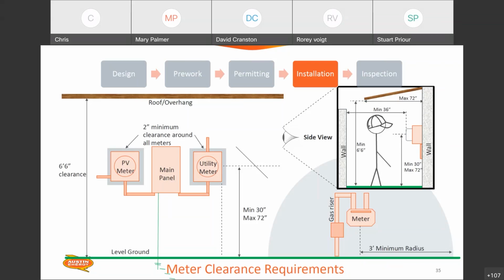You'll see the gas meter there. Regulator on that gas meter is where you need to keep everything out of a 3-foot radius from that gas regulator. That's all electrical components. Conduit, obviously EMT, you can have it run by gas meters, but anything that has a disconnecting means on it that could potentially create sparks is what we will be looking for in that 3-foot radius there. You need to have 6.5 feet of overhead clearance at a service panel. So you need to have safe working room around all of your equipment.